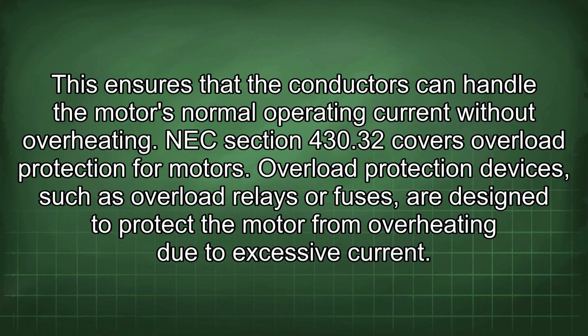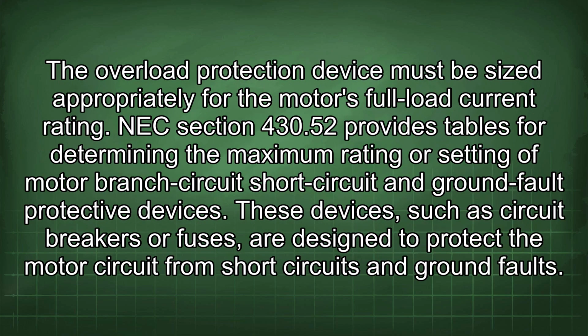NEC Section 430.32 covers overload protection for motors. Overload protection devices, such as overload relays or fuses, are designed to protect the motor from overheating due to excessive current. The overload protection device must be sized appropriately for the motor's full load current rating.